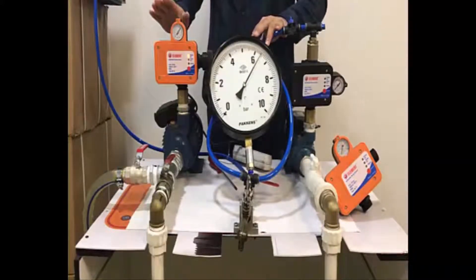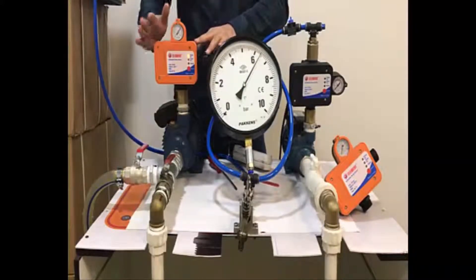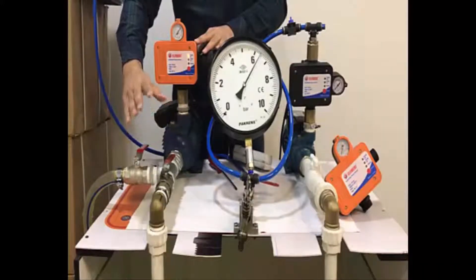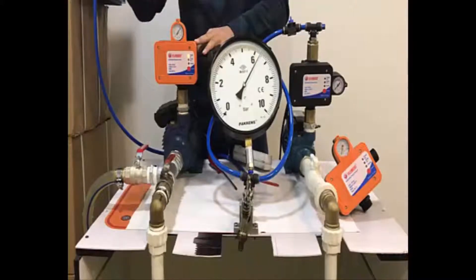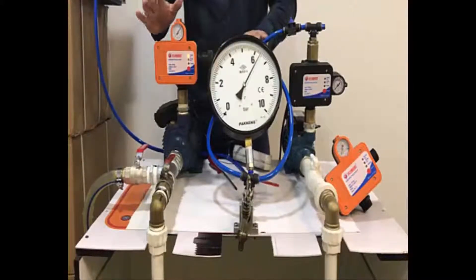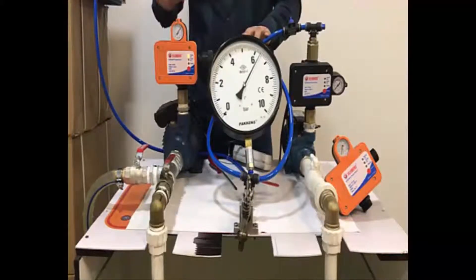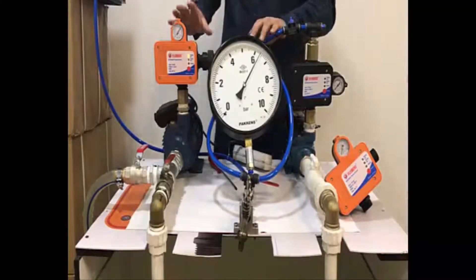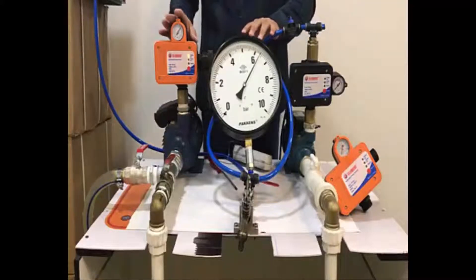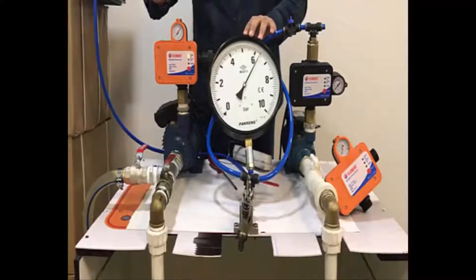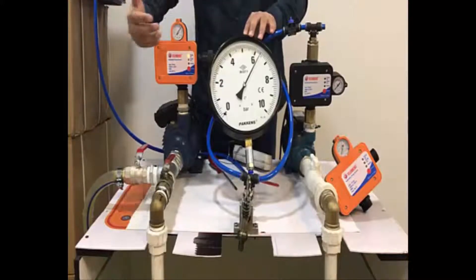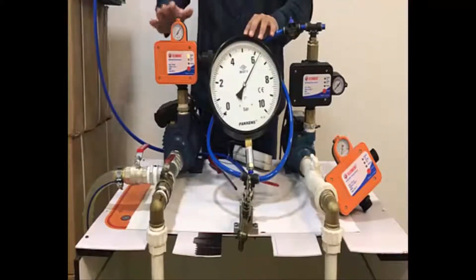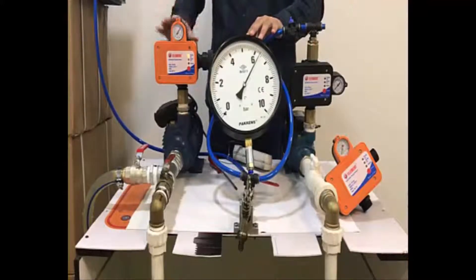As you see, the pump saw that there was no water in the system and it tried. For the first minute it tries every five or six seconds to check if there is water in the system or not. After the first minute it will try every 15 minutes. If the water comes after, for example, 15 minutes or 30 minutes, our device will see it and start to pump again.